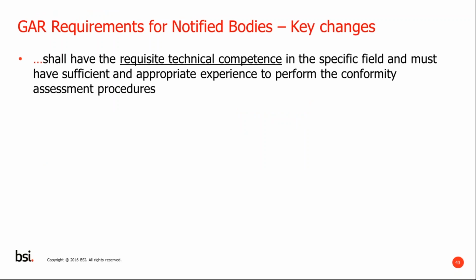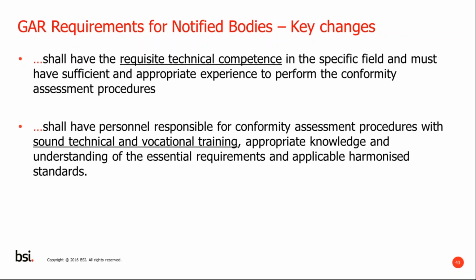So the key changes to this are taken directly from the text. Notified bodies shall have the requisite technical competence in the specific field and must have sufficient and appropriate experience to perform the conformity assessment procedures. It's looking at all the competence of the people.